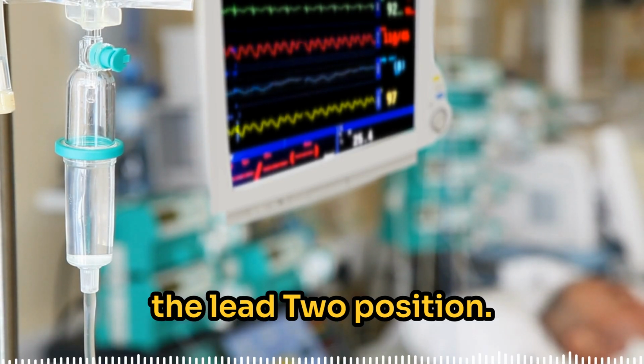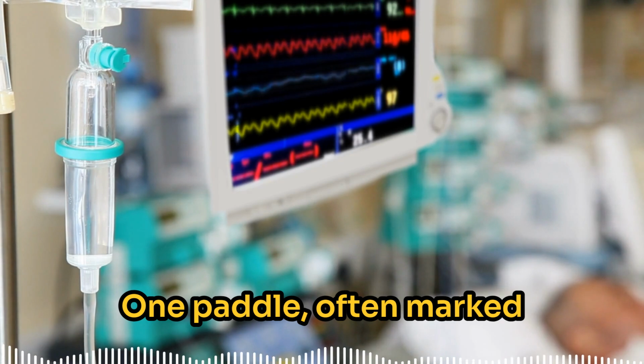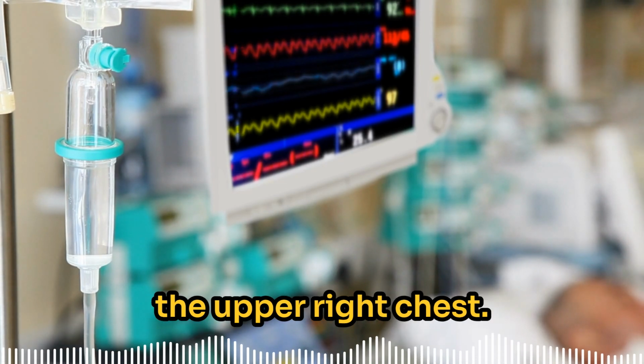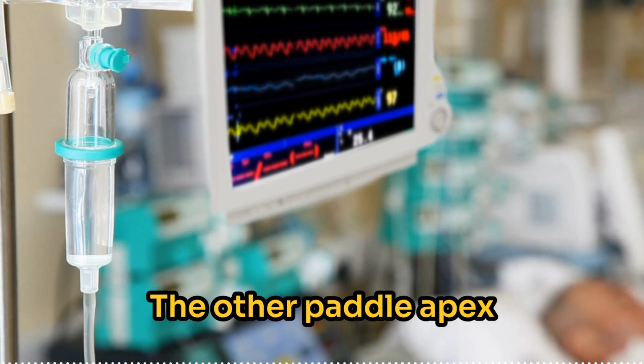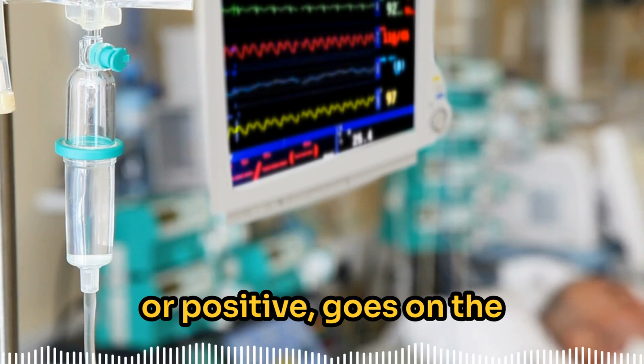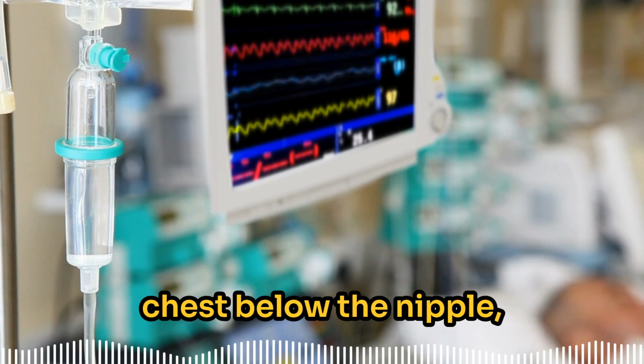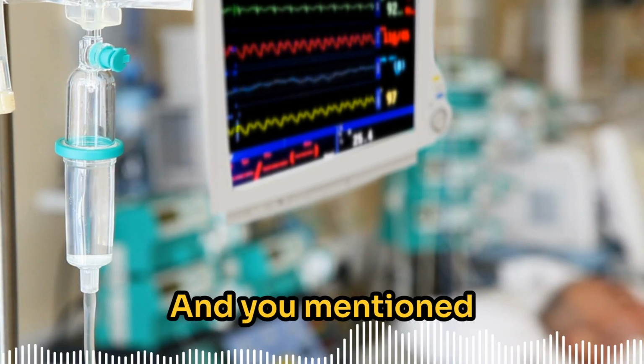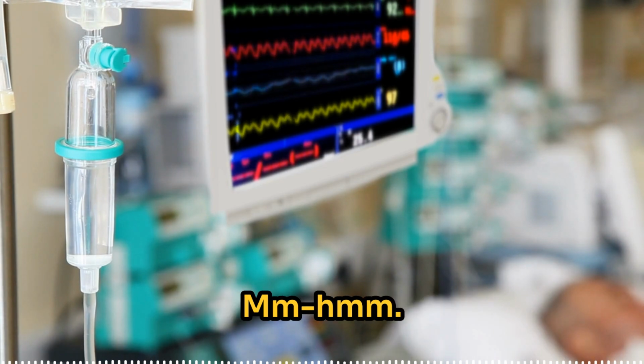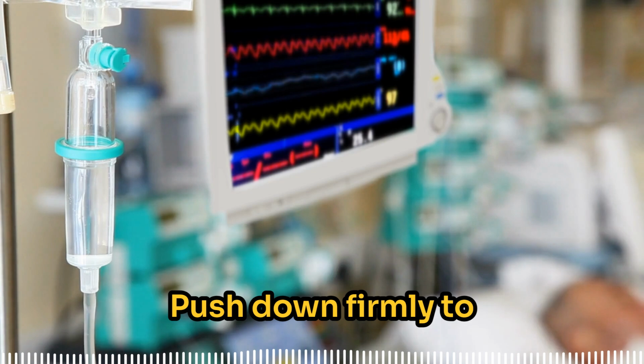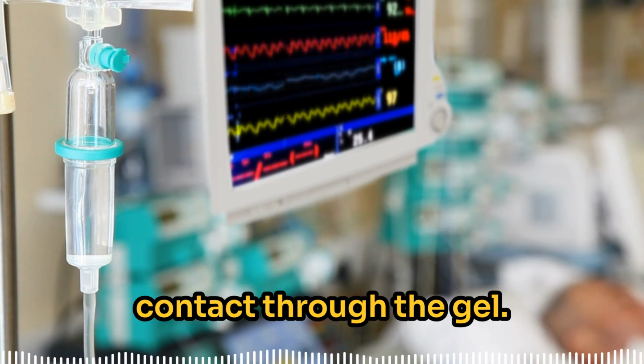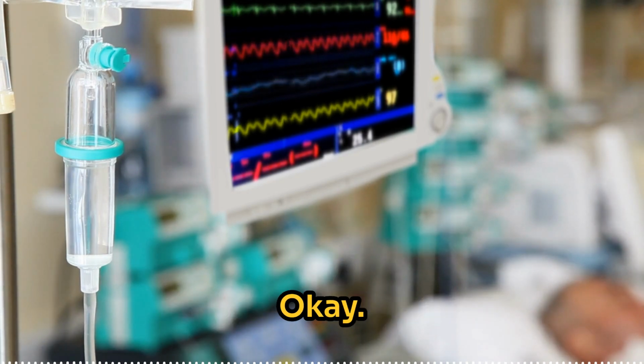Then, if using paddles, position them firmly on the chest. Standard placement is the lead 2 position. One paddle, often marked sternum or negative, on the upper right chest, just below the collarbone. The other paddle, apex or positive, goes on the lower left side of the chest below the nipple, kind of in the armpit line. And you mentioned pressure. Yes, significant pressure, like 25 pounds of pressure, as one source mentioned. Push down firmly to ensure really good contact through the gel. Reduces impedance. Okay. Paddles placed, pressure applied, everyone's clear.